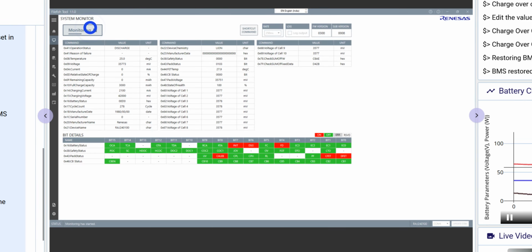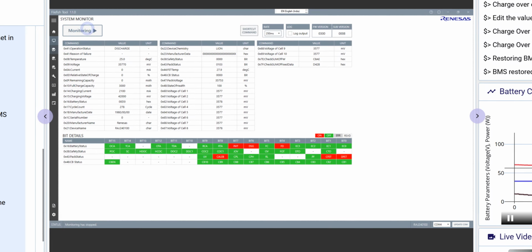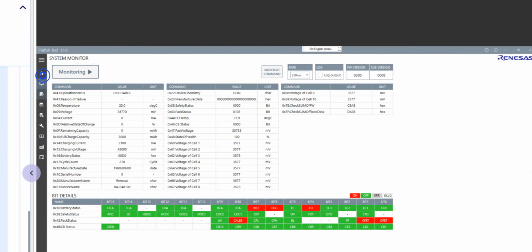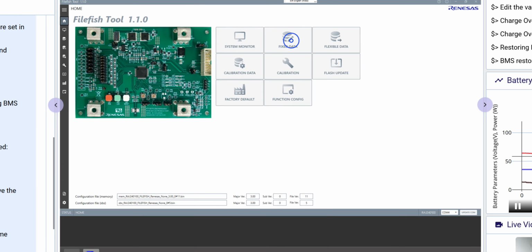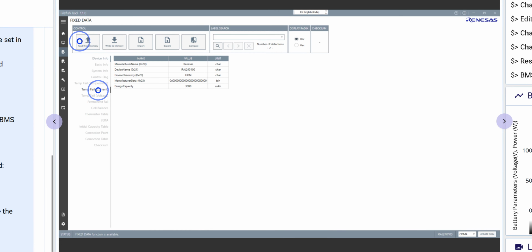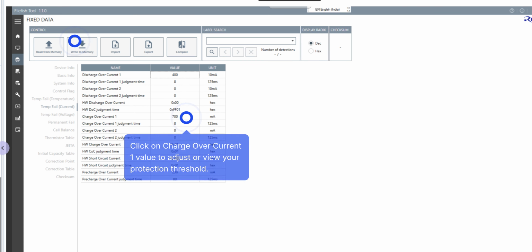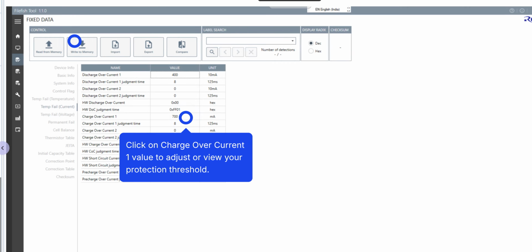First, stop the BMS live monitoring and click the Home button. In the software, select Fixed Data. Then choose Read from Memory to load the existing BMS settings. Navigate to the Temp Fail, Current section, and update the required overcharge current parameters. After making the changes, click Write to Memory to save the configuration to the BMS.